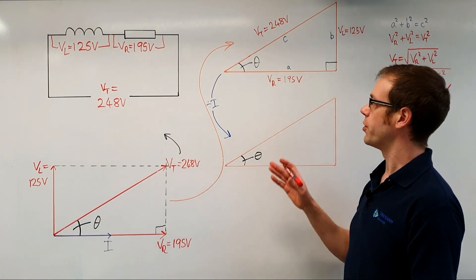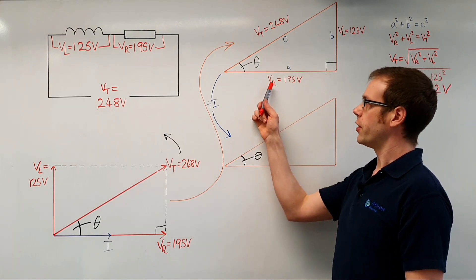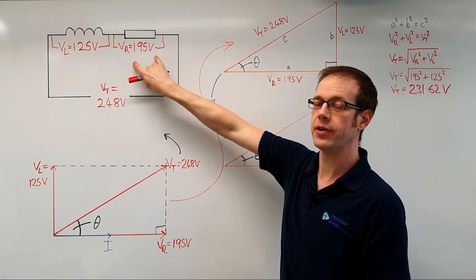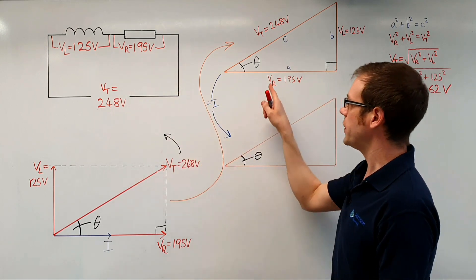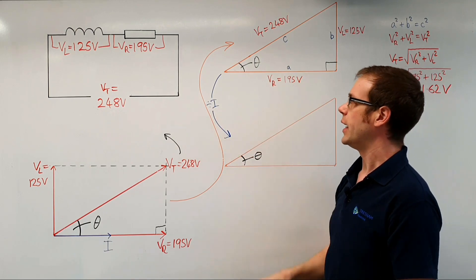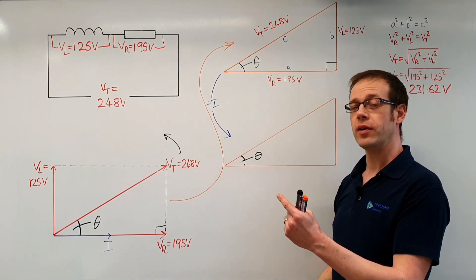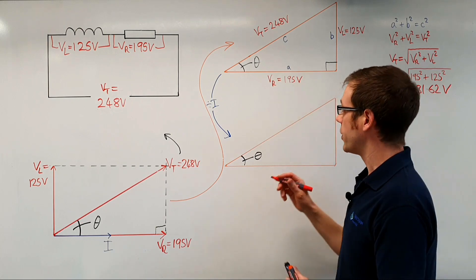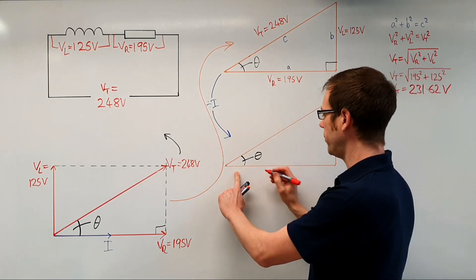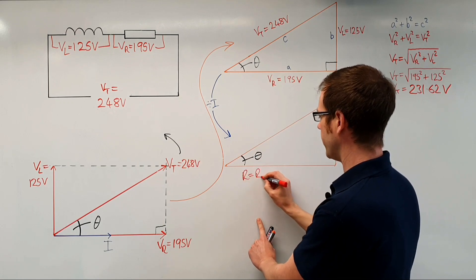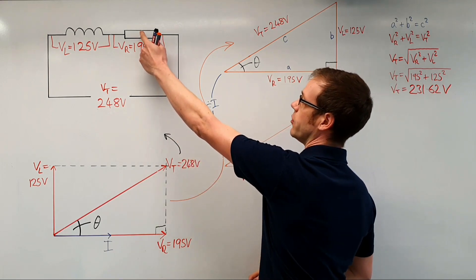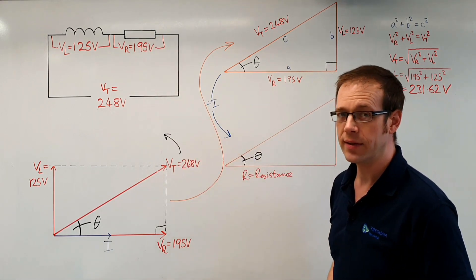Turning our attention back to this triangle, we have VR — the voltage measured across the resistive part of our fluorescent light circuit. If we take that voltage and divide it by the current flowing through the load, it tells us the value of resistance that part of the load has. So V divided by I for this side of the triangle gives us the resistance of the resistive part of the circuit.